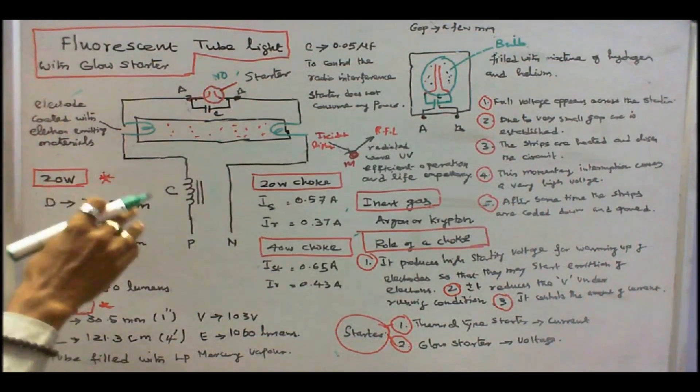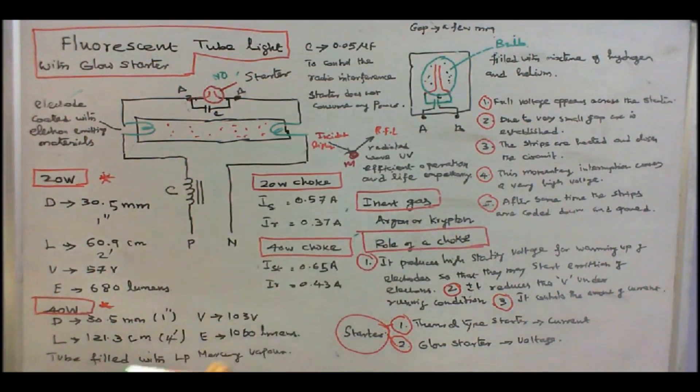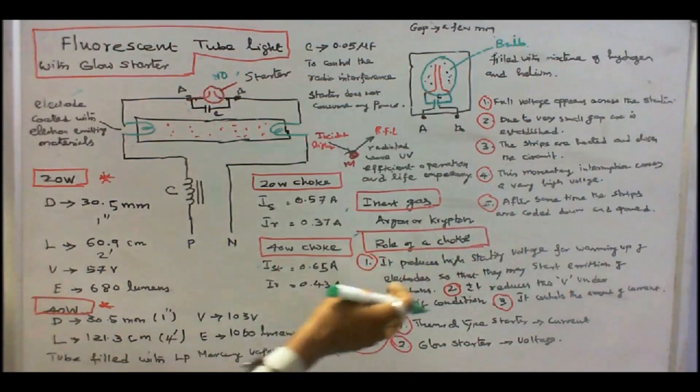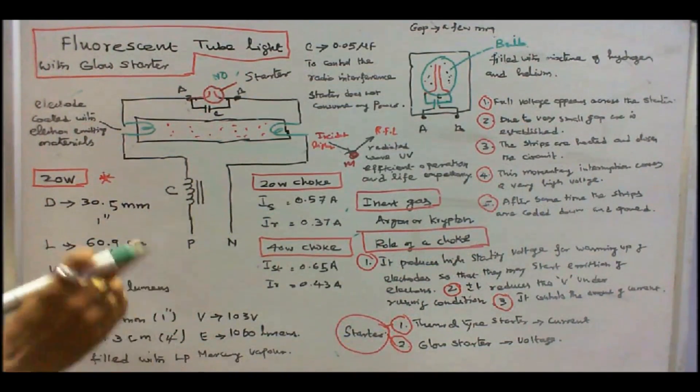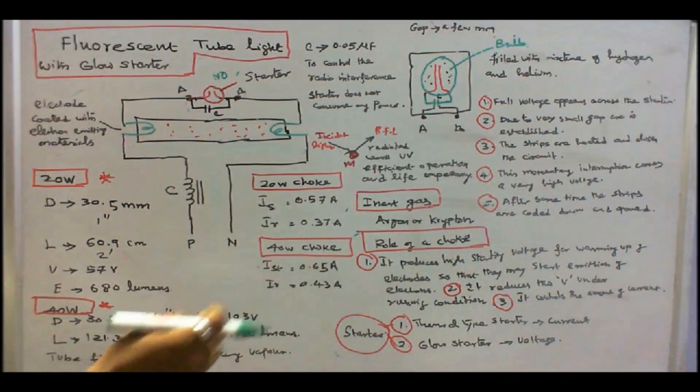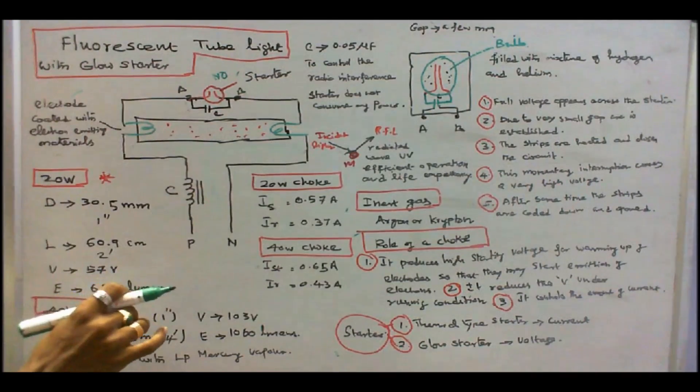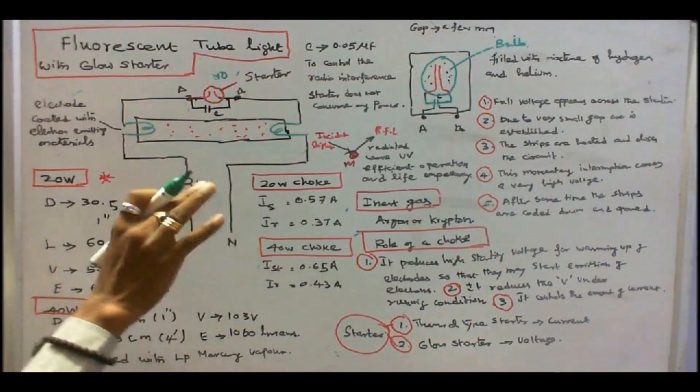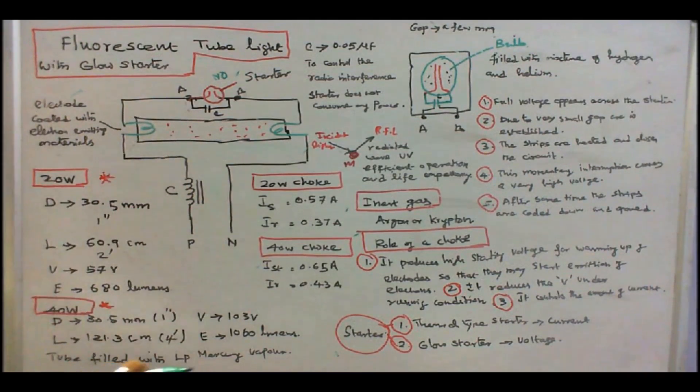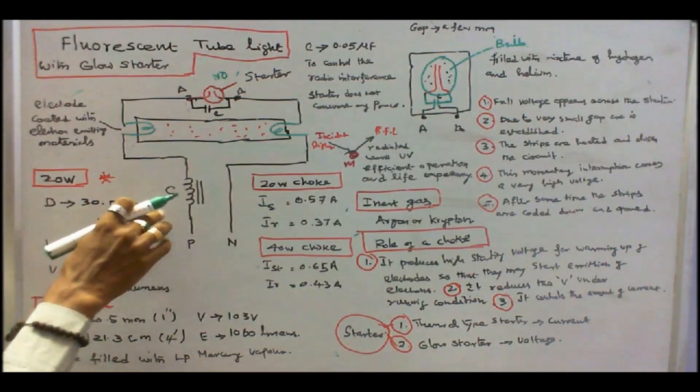So, the role of chokes are, number one, it produces a high starting voltage for warming up of electrodes, so that they may start emitting electrons. Number two, it reduces the voltage under running condition. For starting only, we need 1000 volts. But running condition, 100 volts is enough. But that has to be controlled. Number three, it controls the amount of current. That is the role of a choke.